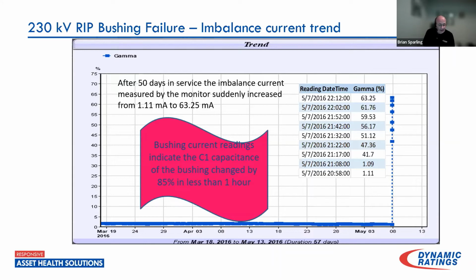Now, when you read the IEEE guidelines for limits in terms of capacitance change on bushings, with offline testing, if the capacitance change is greater than 5% from nameplate, it's time to replace the bushing. Here we have a change in capacitance of 85% in less than 1 hour. Every little blue dot there is a test, and once the monitor sees this fast increase, it's capturing data every 5 minutes or so and able to trend it. So we were surprised, the owner of the transformer was surprised, and the bushing manufacturer was surprised about how quickly things can go south with RIP bushing failures.